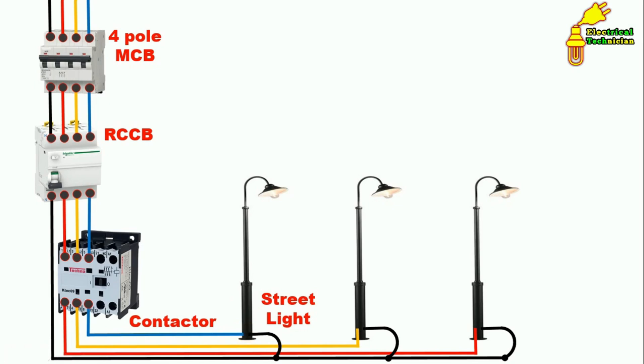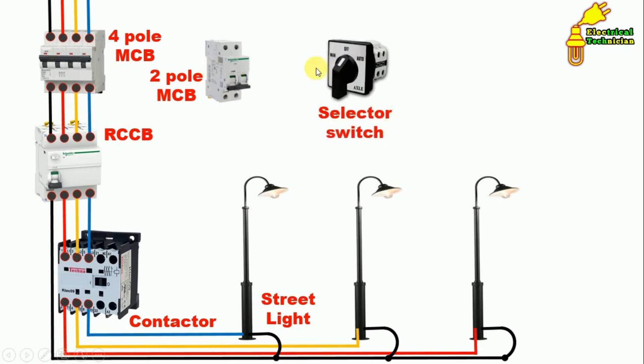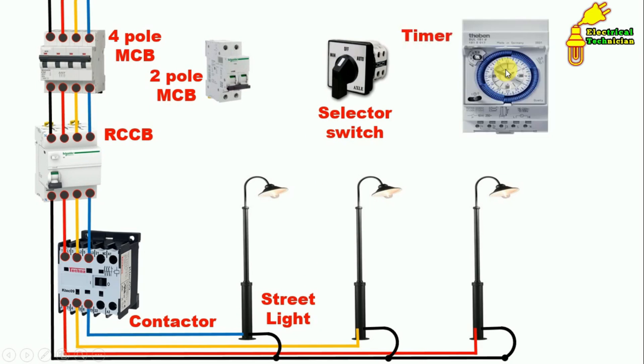Power wiring is completed. Now for protection of control wires, we use a two-pole MCB. After this, we use a selector switch. If we want to turn on in auto mode — that is through timer — we put the selector switch in auto. If we want to turn on manually, we select the manual position. In auto position, lights will turn on through the timer according to the time we set.